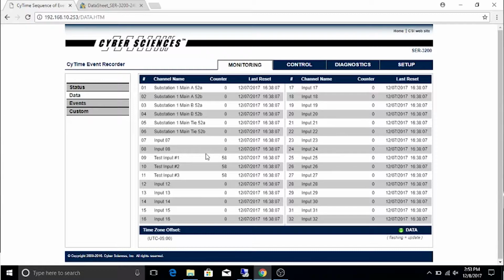Maybe you're going to use this to schedule maintenance on, say, circuit breakers, where you know that after a certain number of cycles of operation, meaning opening and closing, a breaker needs to have maintenance performed on it. You might base your maintenance on calendar date or time since last maintenance. You might base it on number of operations, and then once you perform your maintenance, certainly you can reset your counter.